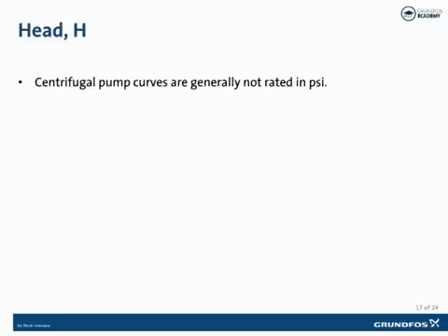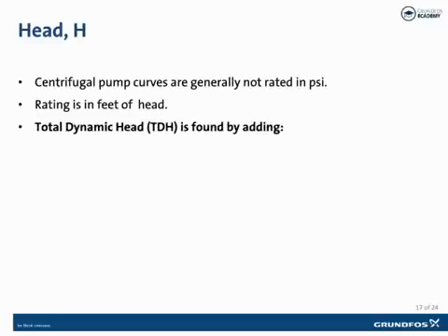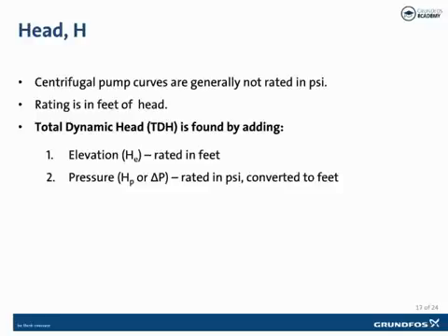Most centrifugal pumps are not rated in PSI or pressure — pumps are rated by the feet of head of the liquid being pumped. This is also known as total dynamic head, or TDH. Total dynamic head is the total equivalent height that a fluid is to be pumped, taking into account the friction losses through the pipe. Total dynamic head is determined by adding together three factors: elevation, rated in feet; pressure, normally rated in PSI which is then converted to feet; and friction loss in the pipe, also rated in feet.